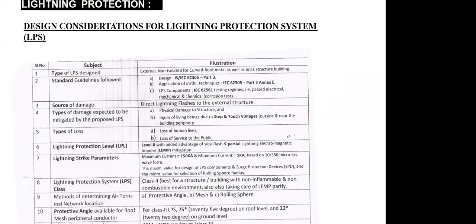Unfortunately, in 2016, if I'm not wrong, in the NBC, the National Building Code, this non-conventional LPS system was discontinued or discarded. So presently, this particular product or application is not available with us, and we need to go with the conventional system only.